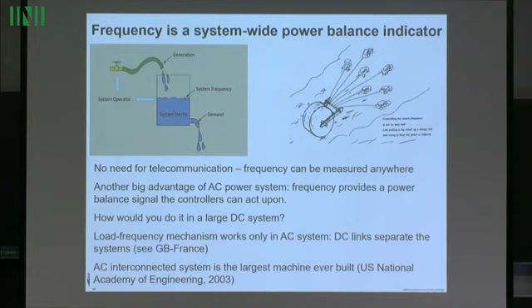This example is for Ireland, a small network with DC links to this country. At one point one of the DC links connecting Scotland with Ireland failed, and you can see big frequency deviations because the system is small and the inertia is small. Frequency dropped from 50 hertz to 48.4, which in Britain would be a big event, and in Europe would be unthinkable - the system would fall apart. In Ireland it's normal, because it's a small system. The bigger the system, the higher the inertia, and the lower the frequency variations.